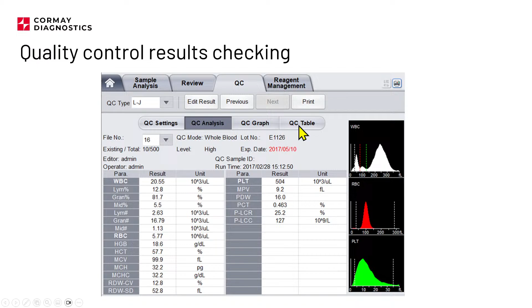So when you are here and you choose the correct level, you just need to prepare your QC sample and present it to the sampling needle and press the aspiration button when you are in this menu. And the analyzer will start the QC analysis. Later, the result will appear on this screen, and we also have an option to see the QC graphs. By default, those will be LJ graphs, and the QC table is also visible. So it's a table view or LJ graphs, as you can see here on the screen.